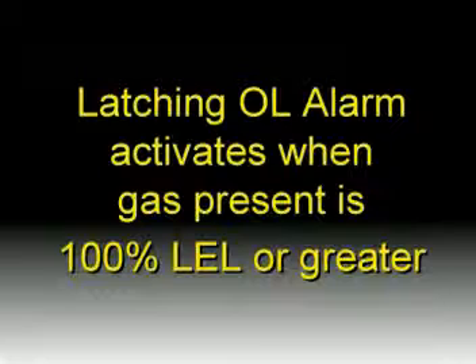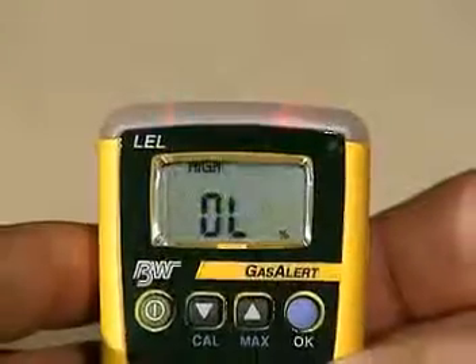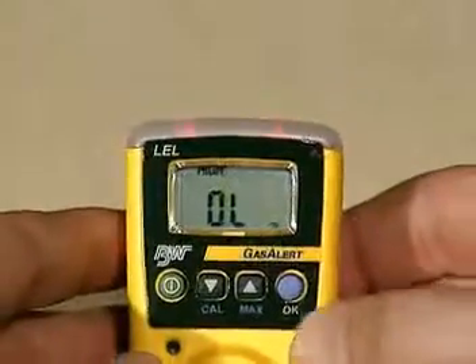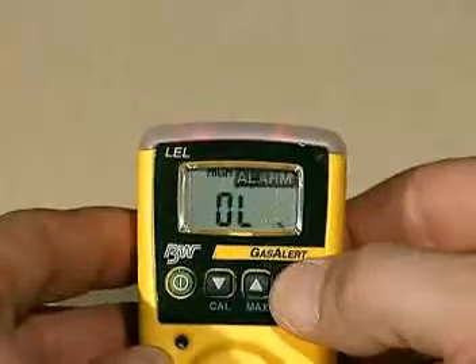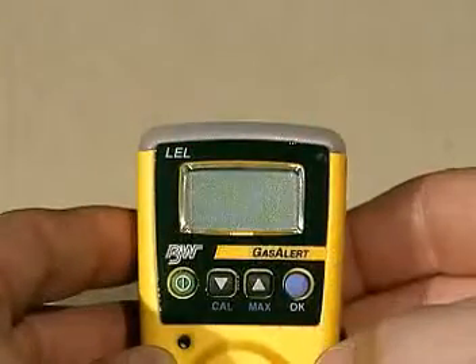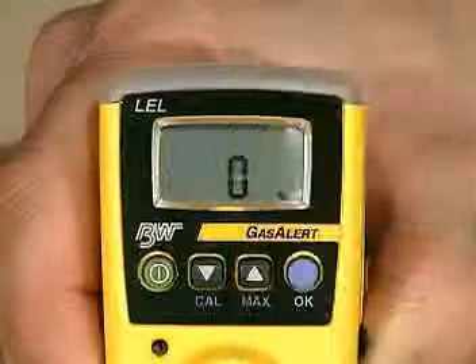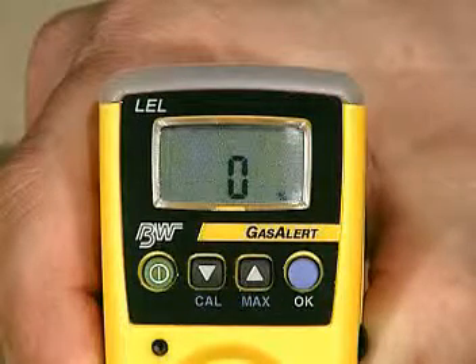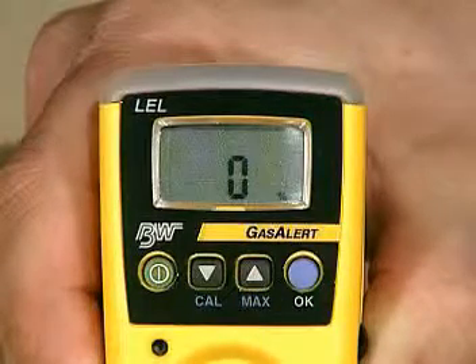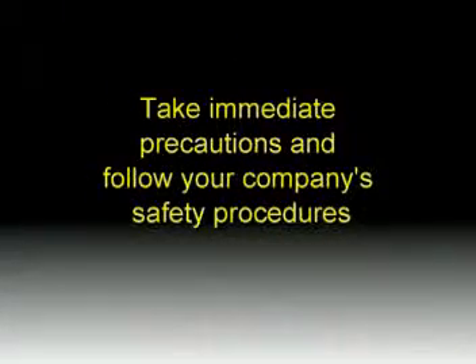The OL or over limit alarm is factory set to latch and activates when the gas present is at 100% LEL. To acknowledge or reset a latched OL alarm, press the OK button. The detector will return to normal operation if the gas present has dropped below 100% LEL. If you encounter a gas alarm, take immediate precautions and follow your company's safety procedures.